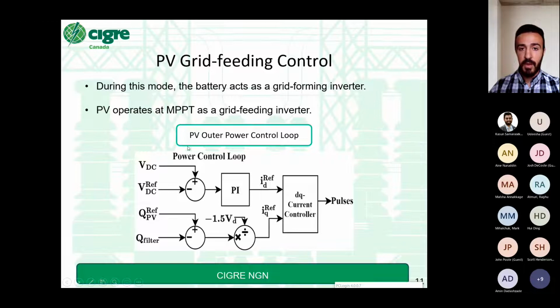And this is the PV outer power control loop. The D axis is going to be mainly responsible for regulating the DC link voltage of the PV VSCs by balancing the power in and power out operation, whereas the Q axis is going to be mainly responsible for regulating the reactive power of the PV VSC.